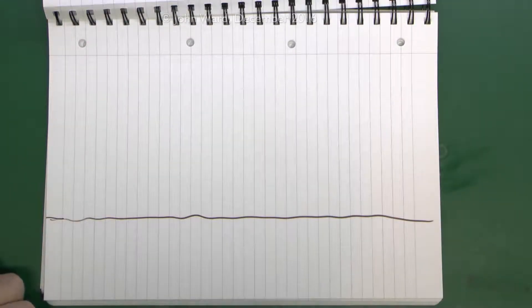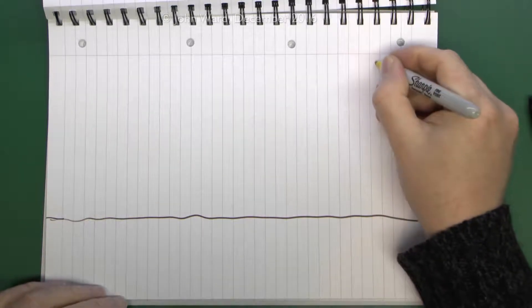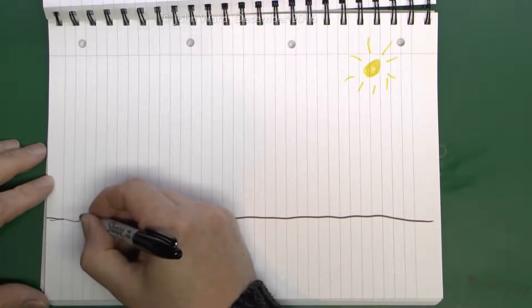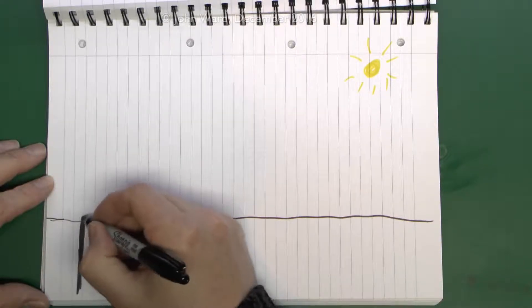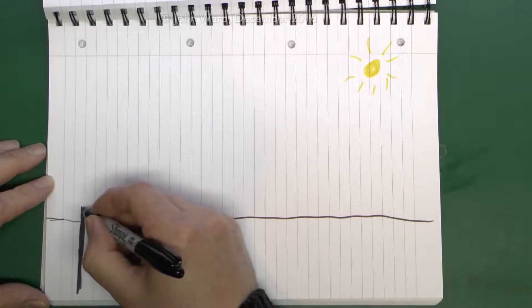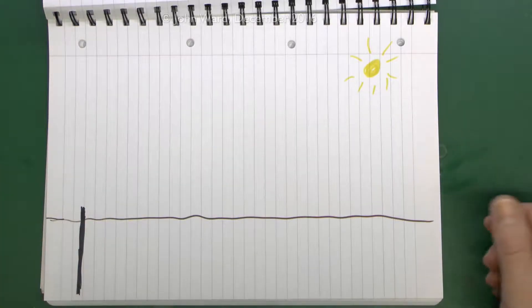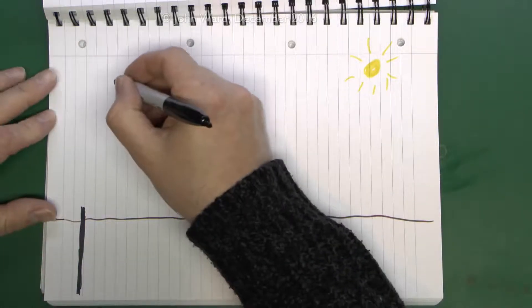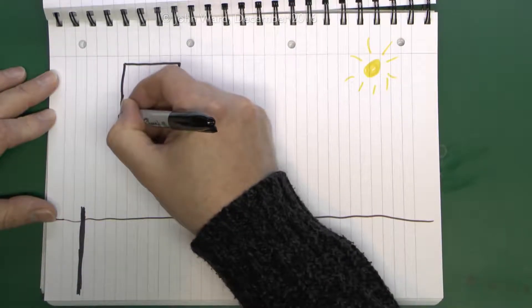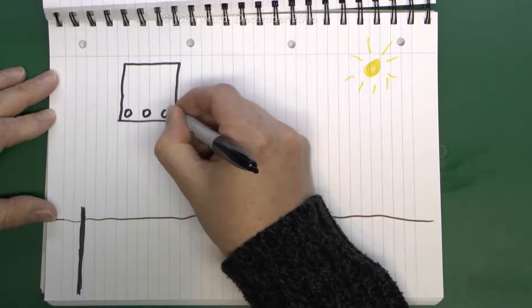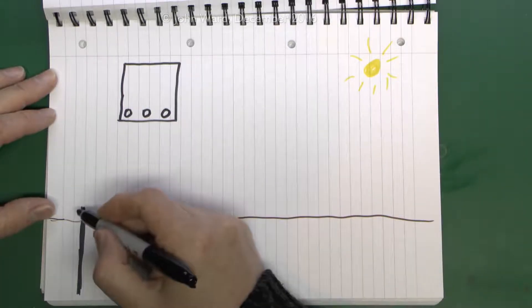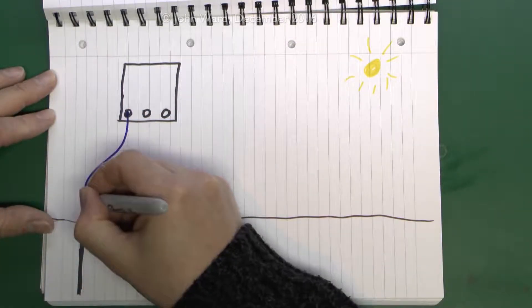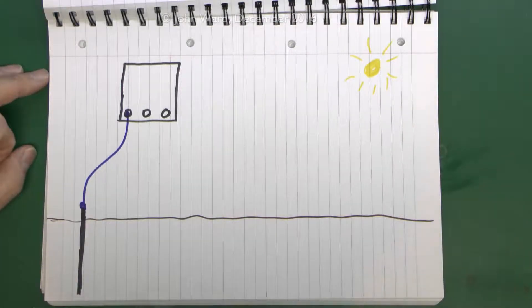You're going to have the electrode installed. Here's the ground here, just drawing it in brown, and here's the sky with the sun in it. Your electrode will be embedded in the ground, and we're going to draw it over here in black. Normally the top is recessed below the ground, but we'll show it above here just for ease of drawing. So that's your electrode that you've installed, and now you need to use the testing equipment to confirm that it's in working order and its impedance is sufficiently low. Typically the testing equipment will have three connections. The first wire just connects over to your earth electrode.